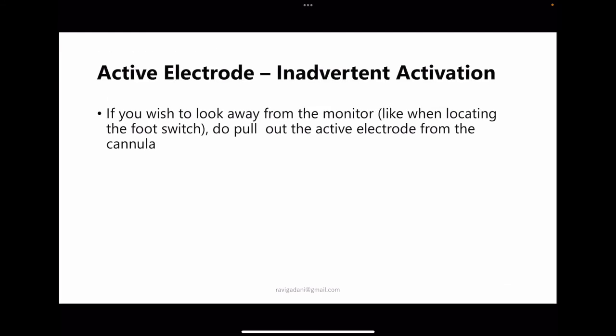Inadvertent activation: consider that you have inserted a monopolar hook for dissection and need to locate the foot switch by looking down. While looking away from the monitor, someone nearby may accidentally push the button and activate the ESU — causing an unintended burn injury to a vital structure. Always pull out the electrical instrument when looking away from the monitor, or when the camera is removed for cleaning.